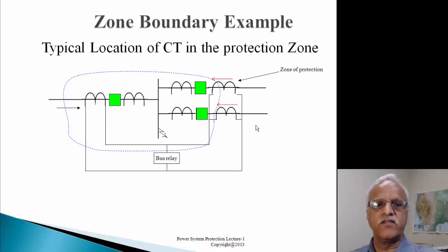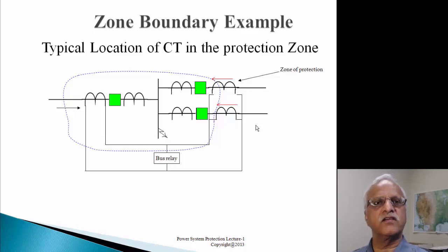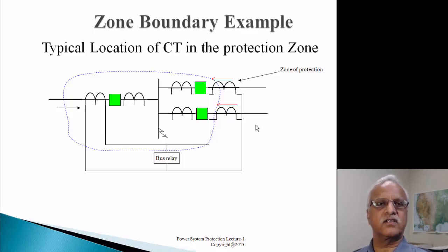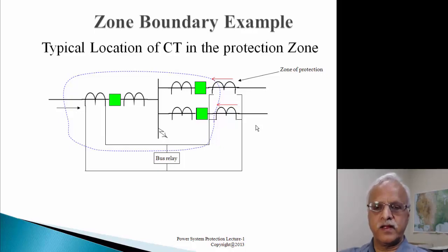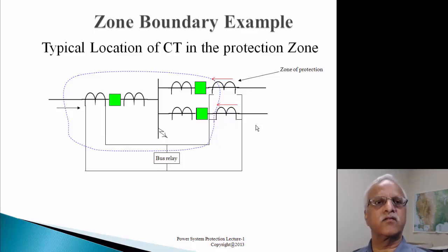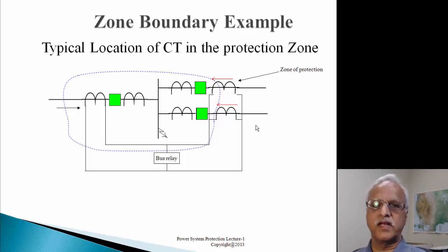As an example: we have the bus and the interrupting device. Outside these interrupting devices, we have current transformers connected differentially - we add all the currents. The sum of all currents at a junction must equal zero. We connect all CT secondaries in parallel and connect a device that monitors the differential current - this is the bus relay. If there is a fault, all currents flow toward the junction, producing a difference current that flows through the relay coil, opening all breakers to indicate a bus fault.